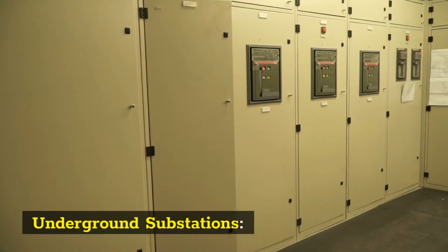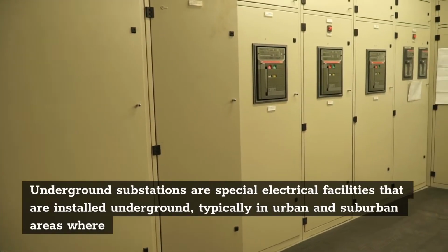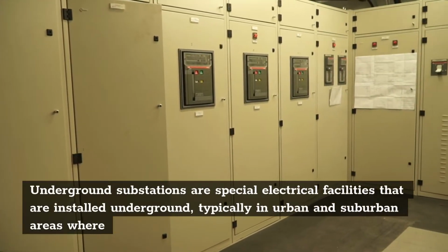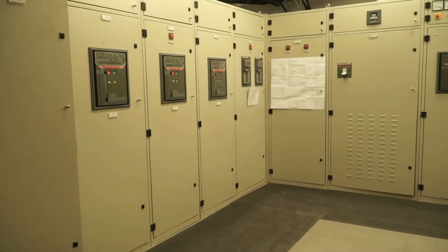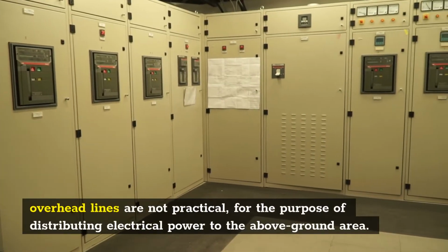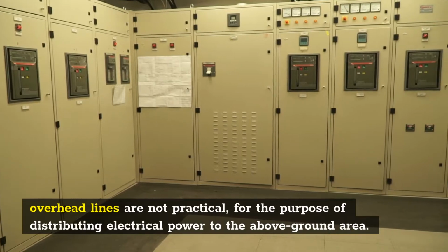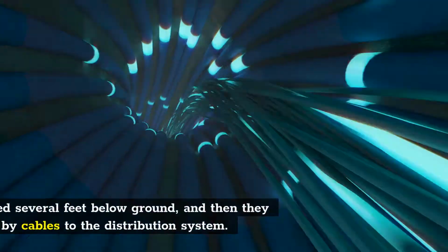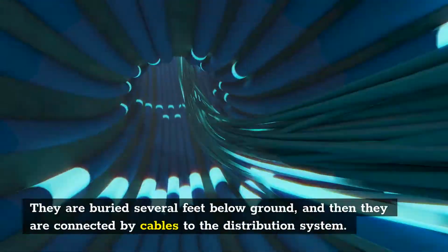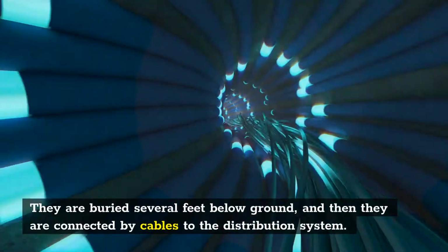Underground substations. Underground substations are special electrical facilities that are installed underground, typically in urban and suburban areas where overhead lines are not practical, for the purpose of distributing electrical power to the above-ground area. They are buried several feet below ground, and then they are connected by cables to the distribution system.